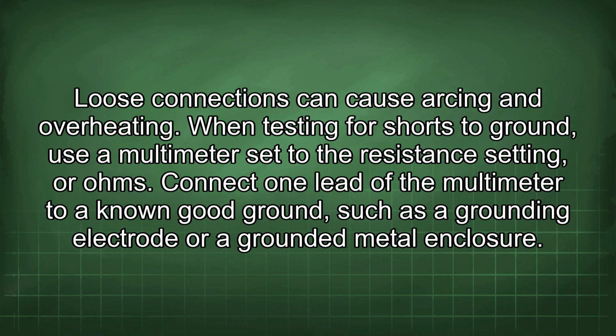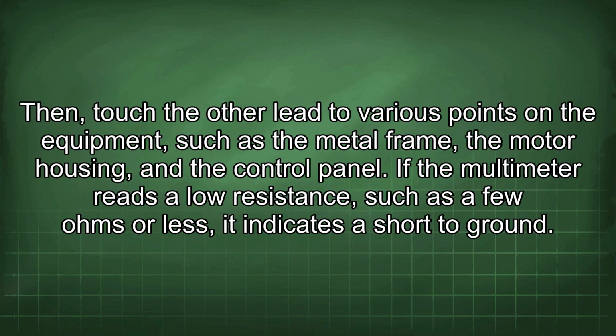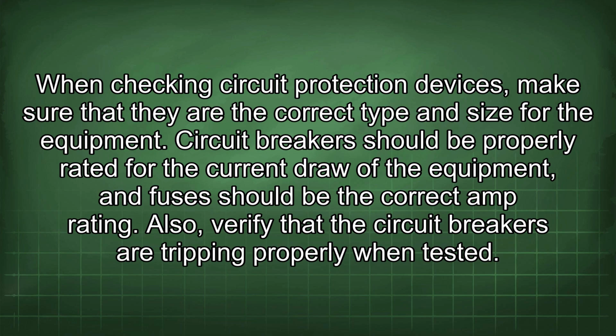When testing for shorts to ground, use a multimeter set to the resistance setting, or ohms. Connect one lead of the multimeter to a known good ground, such as a grounding electrode or a grounded metal enclosure. Then touch the other lead to various points on the equipment, such as the metal frame, the motor housing, and the control panel. If the multimeter reads a low resistance, such as a few ohms or less, it indicates a short to ground.